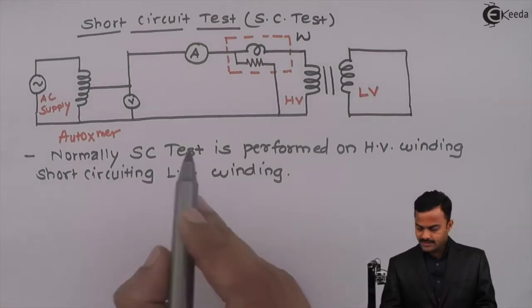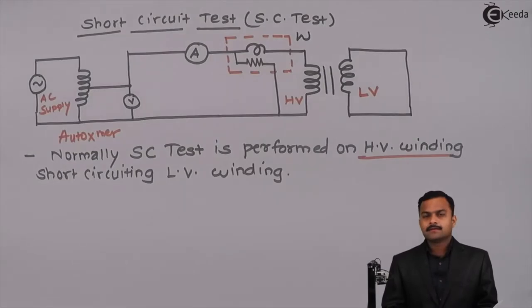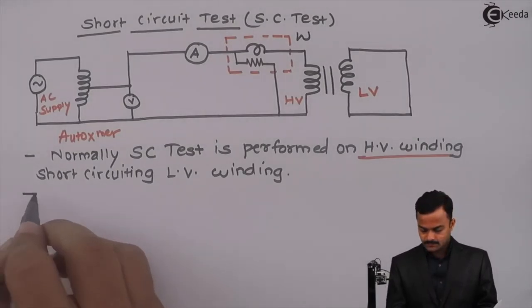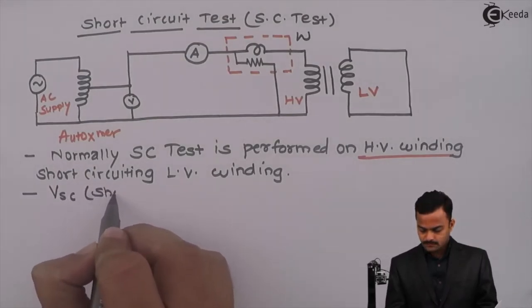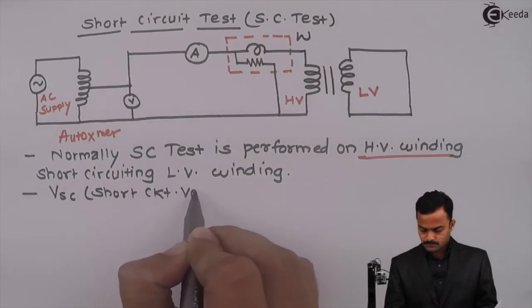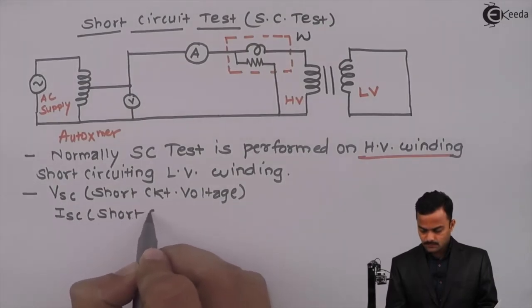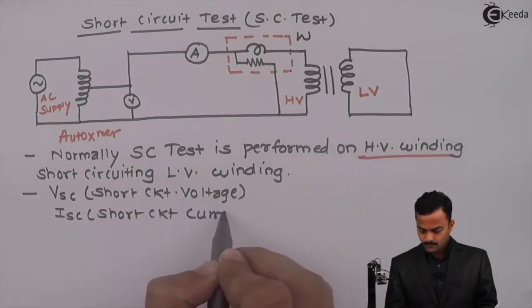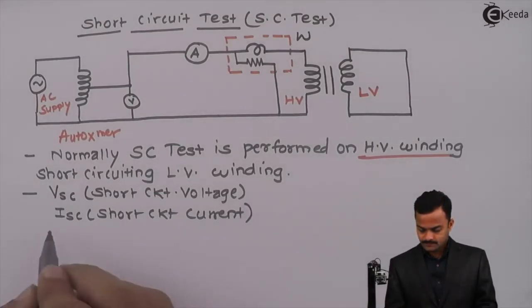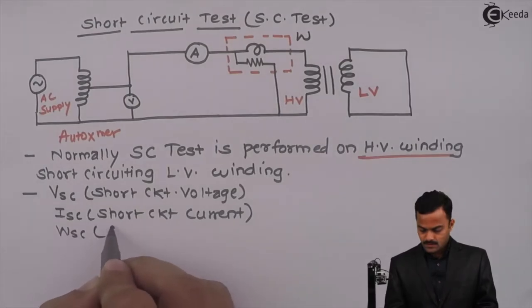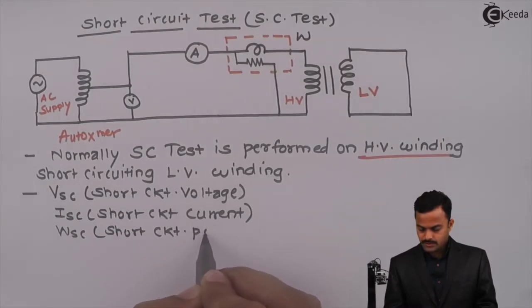So, short circuit test is performed on the high voltage winding. The readings we get are VSC — the short circuit voltage; ISC — the short circuit current, which is comparable with the full load current; and WSC — the short circuit losses, or short circuit power.